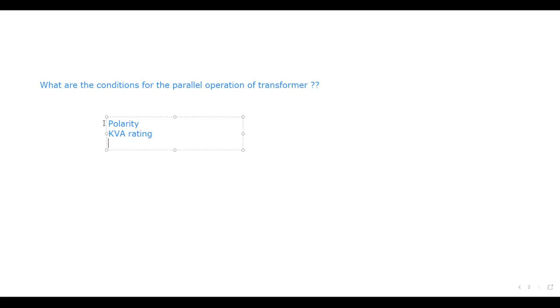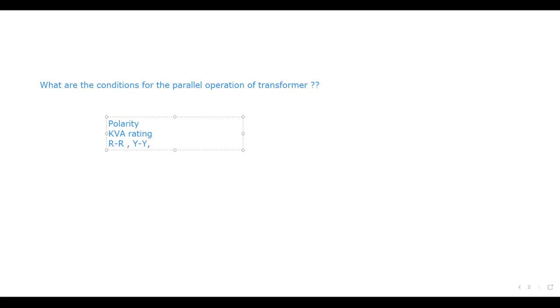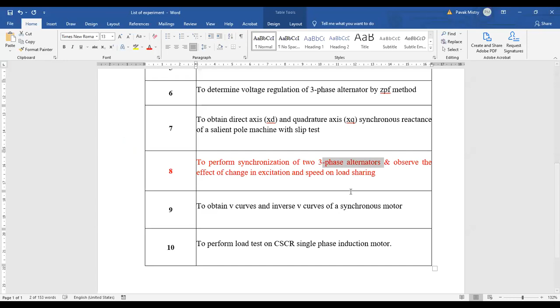Okay, so these are the important points before you connect any transformer. First, you should take care of the polarity. You should also take care of the KVA rating. Then the frequency of supply should be the same. If it is a three-phase transformer, we should also look at the phase sequence. So R should be connected with R, Y with Y, and B with B phase.